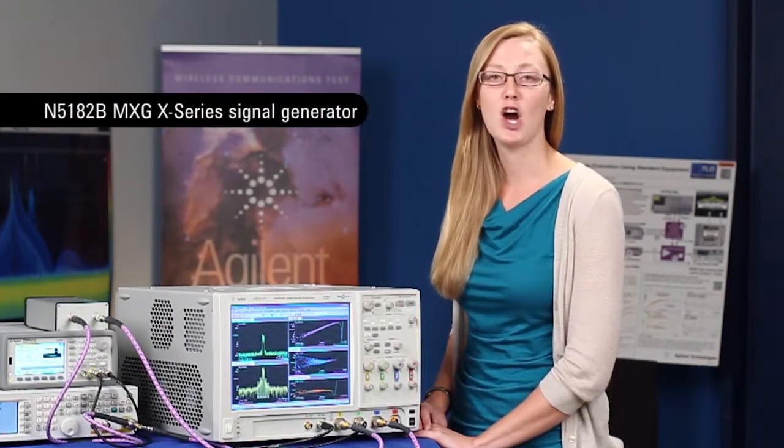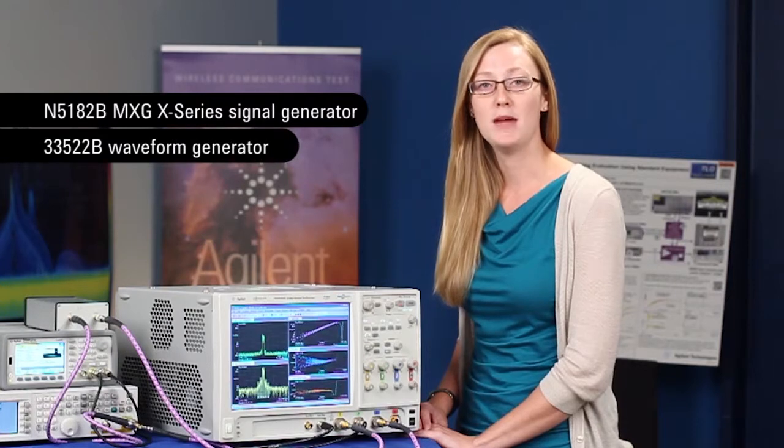The MXG signal generator is providing the RF input signal to the power amplifier. The 33522B arbitrary waveform generator is providing the envelope signal to the envelope tracking power supply. If you want to see more on how to generate these test signals, watch our previous video on envelope tracking.